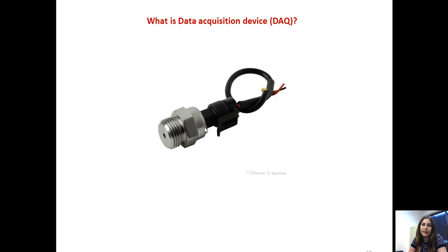And there's another thing, called the input voltage, meaning that your sensor has to be connected to some input power or voltage to be operated. And most of the time, it's a DC voltage again. So for example, this sensor needs 9 volt DC to operate. Once you have provided that 9 to 10 or 12 volts DC to that pressure transducer, it can give you the results in terms of the pressure that it is reading, from 0 to 3 volts DC. So there are 3 things.